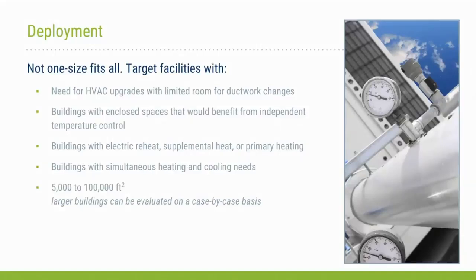Potential project characteristics may include the need to upgrade the HVAC system or to add cooling. Project space constraints, such as limited room for ductwork, minimal clearance, or minimal space for equipment, can be reasons to consider VRF. Projects that have multiple separate spaces with various heating and cooling needs that would benefit from precise, independent temperature control are also good candidates for VRF.